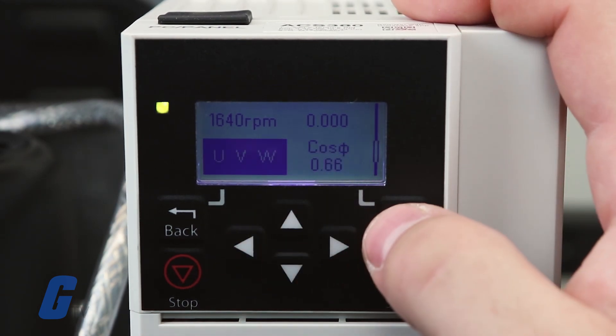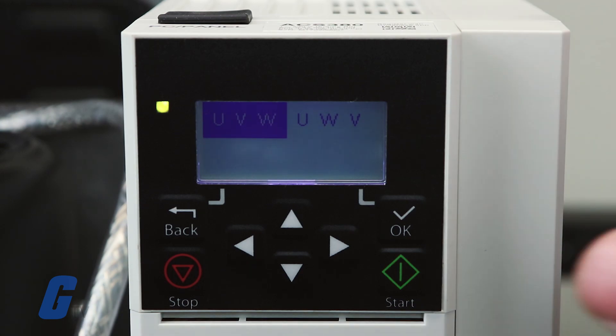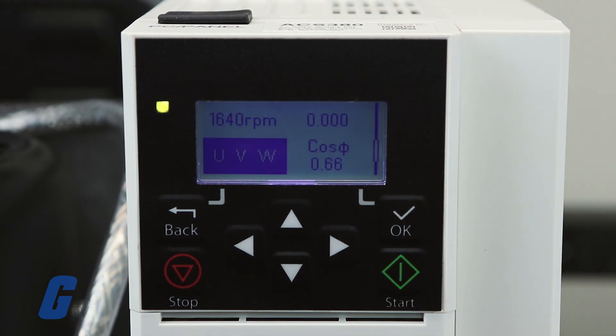Examine the direction of the motor. If it is rotating in the incorrect direction as displayed, you can reverse the direction using either the phase order setting or with the phase order of the motor cable.